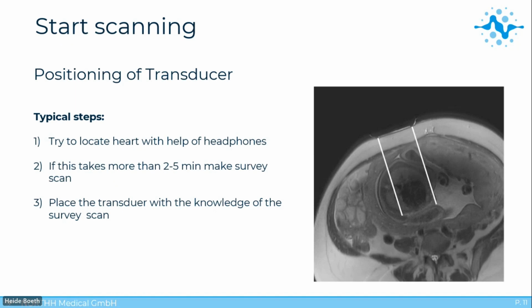When it comes to positioning the transducer, we haven't seen big problems at all. On the right side, you can see an image of how the transducer is placed, centered above the heart. That is actually the key. Have the transducer focused above the heart, so the fetus can move as much as possible and will still stay within the acoustic window of the transducer.